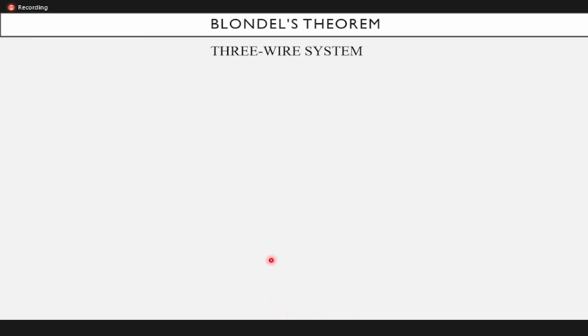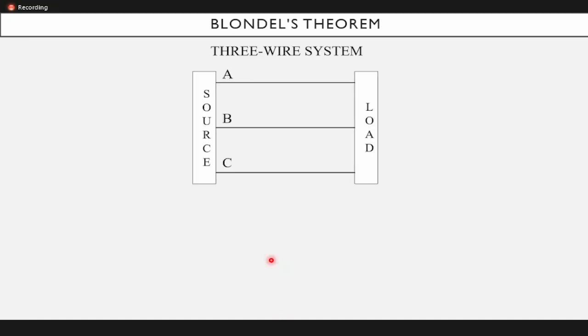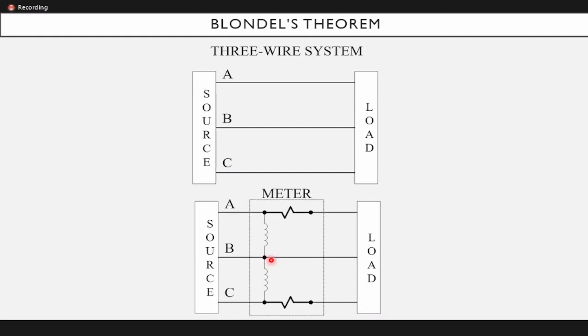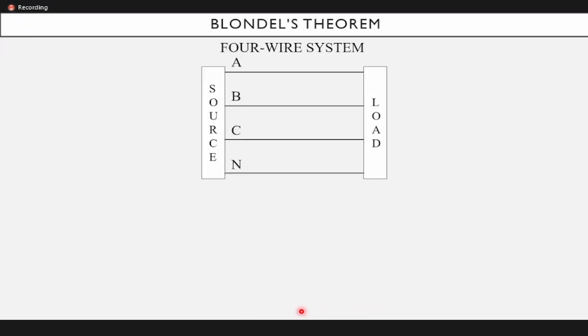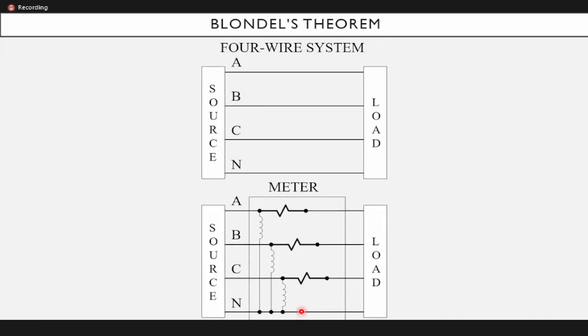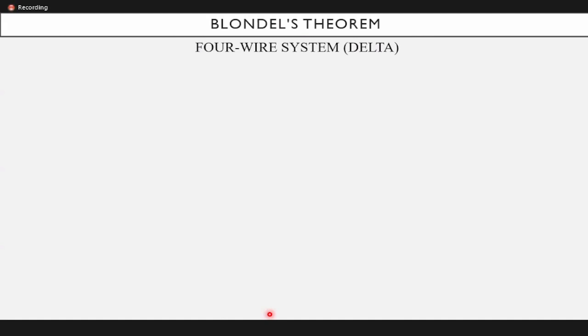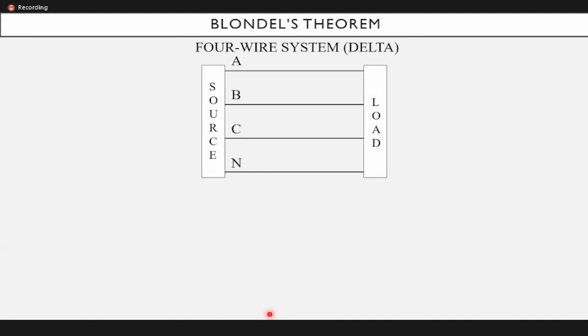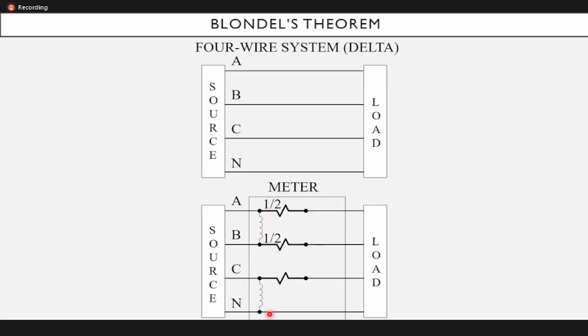The three-wire system is the old metering setup. This is ungrounded, floating phase B, no current coil, just the potential coils, and only phase A and phase C have the current coils. The four-wire system is the typical polyphase connection. There are complete potential and current coils connected to its phases and to the ground. The four-wire system delta is also our old metering setup.